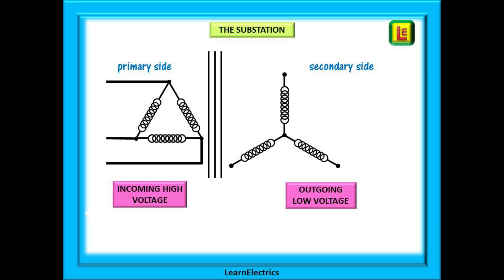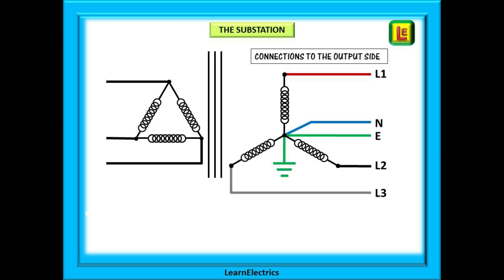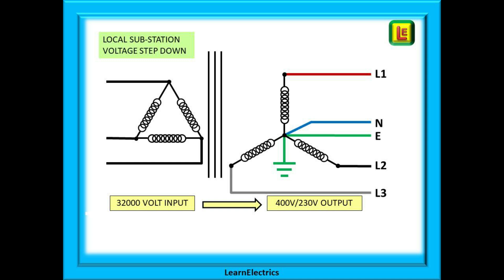On the right is the output side, the outgoing low voltages. This arrangement looks like a star and this is the secondary side of the transformer. Looking at the output side we now have a neutral together with the three phases and an earth. The substation is going to step down the voltage. That is to say a high voltage is input to the transformer and a lower voltage, a stepped down voltage, is output. Here we have shown a 32,000 volt input and a 400 and 230 volt output.